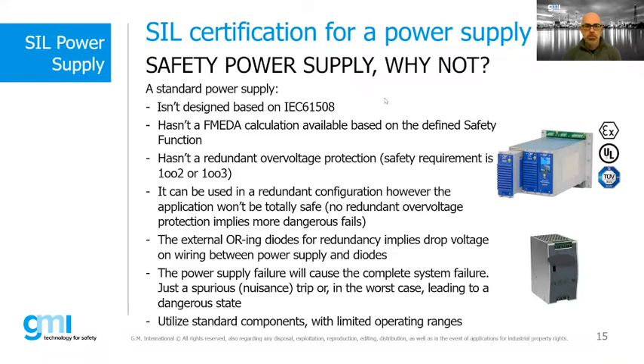So, why is it correct to use a safety power supply system? Below are the main reasons that lead us to advise against the use of a simple standard power supply. A standard power supply is not designed based on the directive of IEC 61508. No calculation is made for the safety function to be obtained. It does not allow redundant protection for overvoltage, while in a safety power supply system, redundant protection is a fundamental requirement. And again, standard power supplies can be used in a redundant configuration, but they do not guarantee that our application is totally safe, for the reason related to the common faults which we have seen previously.